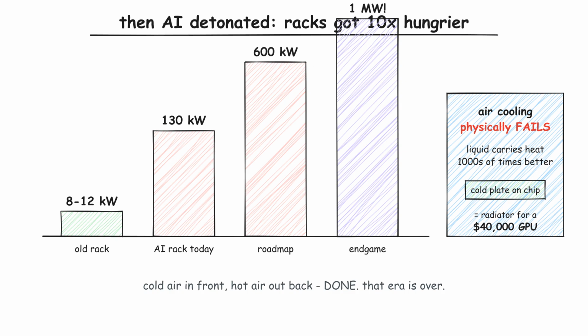Here's what changed. For 20 years, a normal server rack drew maybe 8 to 12 kilowatts, and the fix for heat was simple air conditioning, cold air in the front, hot air out the back. The average rack across the world's data centers still sits under 10 kilowatts. An AI rack draws over 10 times that, and the roadmap keeps escalating. Chip designers are already talking about 600 kilowatt racks, and eventually a full megawatt in a single cabinet.